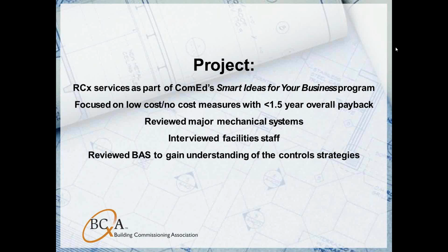Issues that we'll get into a little later with the chiller plant. We reviewed the BAS with the facilities staff to gain an understanding of the control strategies being used in the building and how the systems operate. And very importantly, we set up a lot of trending. Good trends are the best way to baseline a building's operation, so at least you can capture that for later use. And it's also a requirement for the utilities retrocommissioning program. So good trends up front.